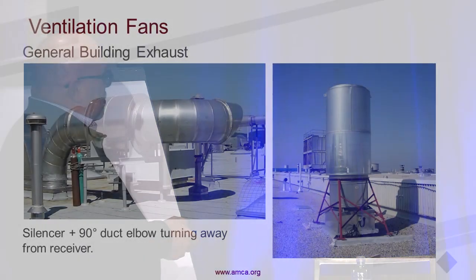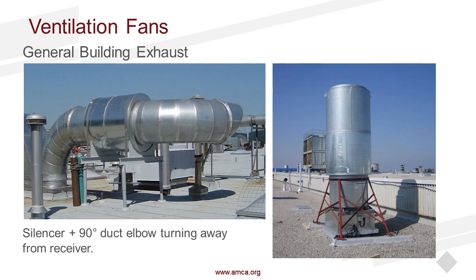And the neighbors were complaining about the noise. There were many of these general exhaust areas and clean air off of processes. So there's a circular silencer here and a saddle brace, external saddle brace support here. And then there's a 90-degree gored elbow, 5-gore elbow here, and they actually turned that away from the neighbors. So kind of did a double duty to fine tune the noise reduction.